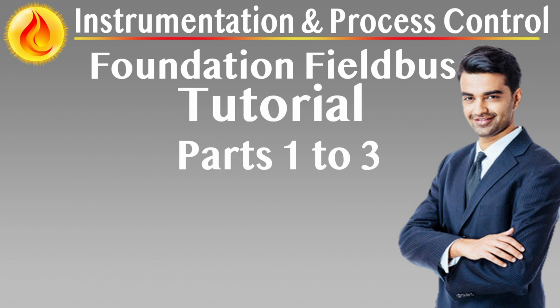Specification for Foundation Fieldbus, Part 3. Communication Model. The Foundation Fieldbus communication model is designed around a layered architecture to ensure structured, reliable, and deterministic communication across field-level devices in industrial automation environments. It aligns with the simplified Open Systems Interconnection (OSI) model, implementing three core layers: physical layer (PHL), data link layer (DLL), and application layer (APL).